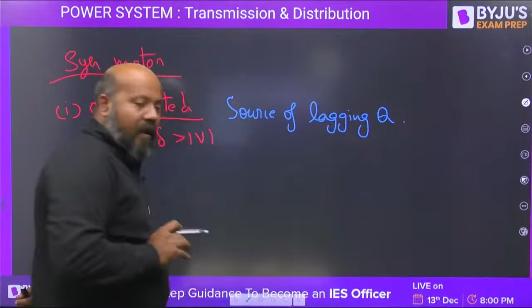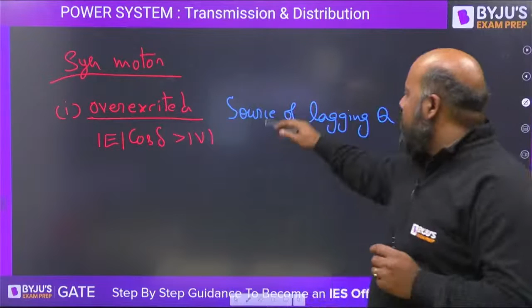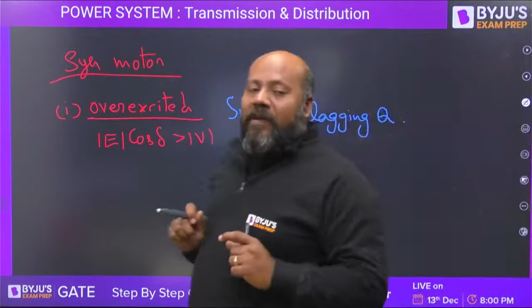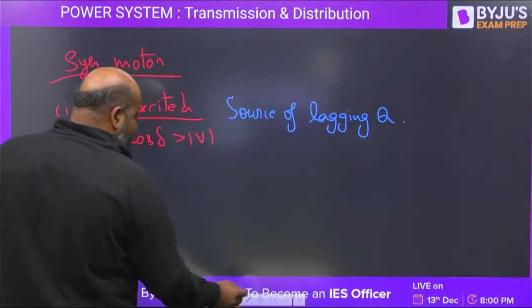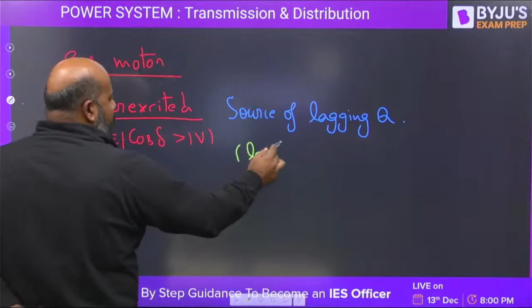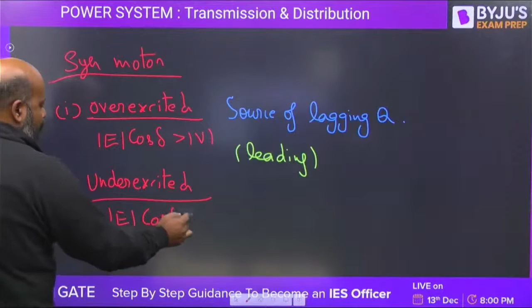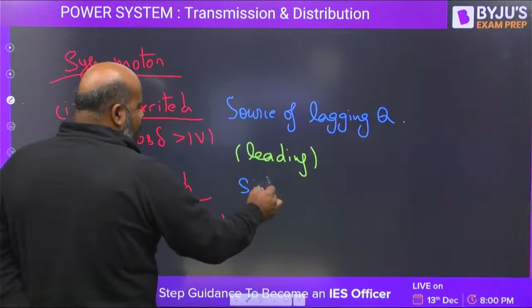Now you tell me, the basic nature of motor is to absorb power, but here it is supplying the lagging reactive power. If something is supplying lagging reactive power, it means it is absorbing the leading reactive power. So what is the operating power factor? The operating power factor becomes leading. I hope you are getting my point. Second is underexcited condition. For the underexcited condition, mod E cos del is less than mod V. Now your synchronous motor acts as a sink of lagging reactive power. So what is the operating power factor? Now the operating power factor is going to be lagging.